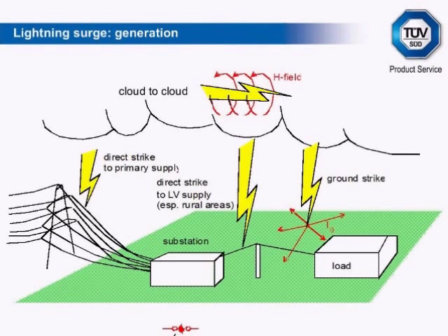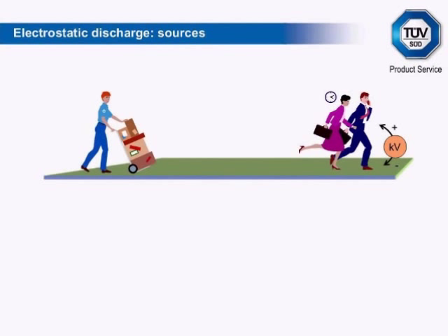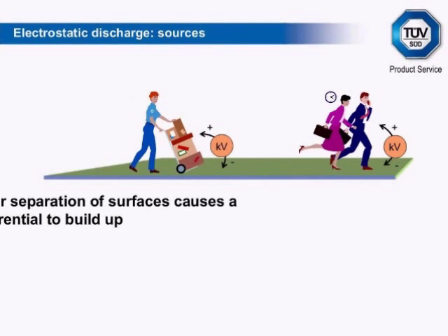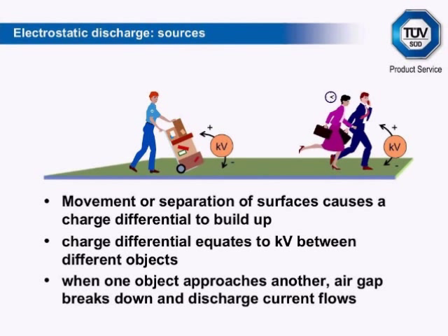The ESD immunity test is intended to simulate the threat from a nearby or direct discharge from a charged person. It does not represent other sources such as furniture or vehicles. When movement occurs between two surfaces, the triboelectric effect causes a separation of charge between them, building up an electric potential on each surface and by extension on the body beneath. This charge is then equalized when the body touches another object. If that object is electronic apparatus, the resulting discharge current can cause malfunction and even damage to sensitive electronic components.